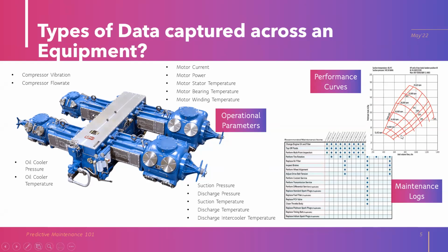Then there's a kind of performance curve for the compressor. You'll have head, or total head, and volume, and based on different efficiencies, how that flow has to move according to that total head. This is the performance curve it should ideally follow. Any deviation from it is an insight that the equipment is not performing optimally.